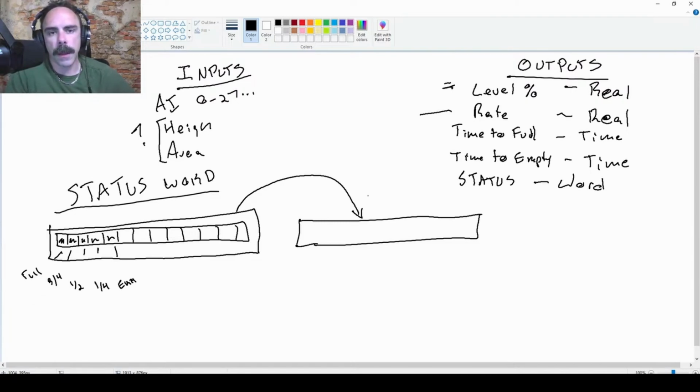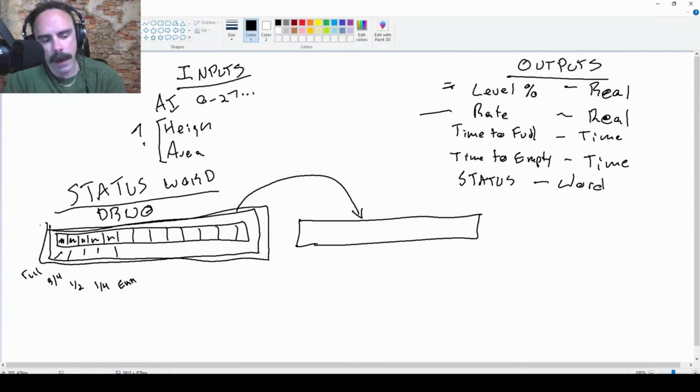Now, if you've ever done this in Siemens Step 7, the previous version of software, it was really simple because it didn't have tags. You were inherently referencing memory. And so all you would do is reference these bits and call DBW0, which is this whole thing, but inside of it you would go DBX0.0, DBX0.1. And so in your logic you would use it like this down here.